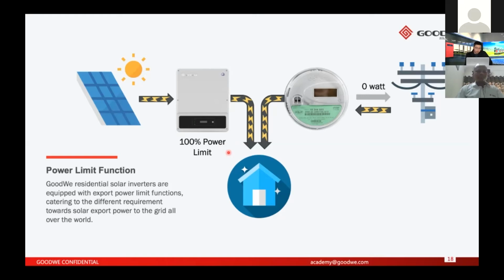Under this activated function, no more power will be fed back to the grid. The loads here can be powered by the PV panels, and can also be powered by the electricity we buy from the grid simultaneously. So you can still buy power from the grid for sure, but there will be no power fed back to the grid. That's called the power limit function.